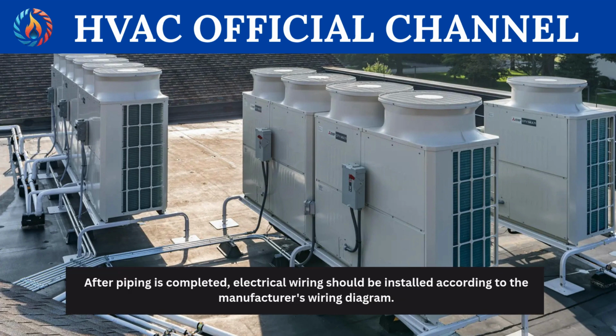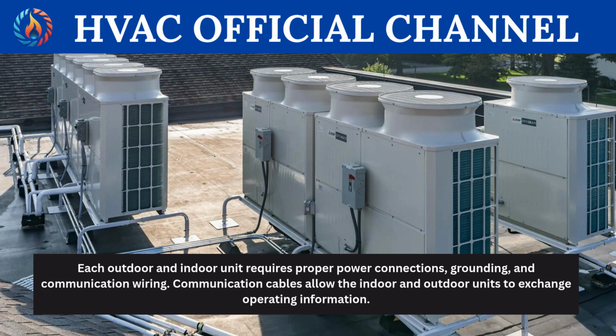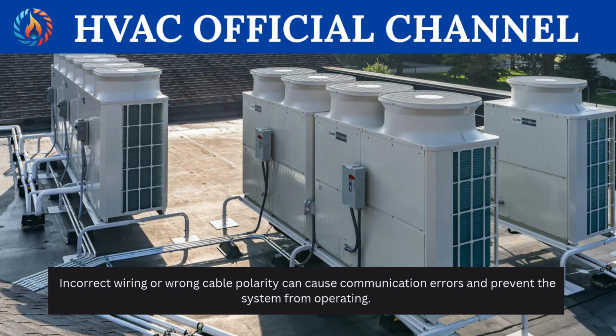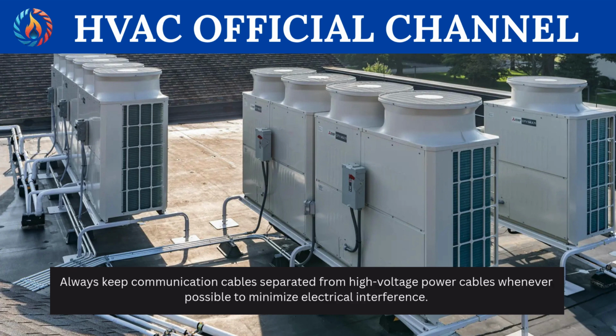After piping is completed, electrical wiring should be installed according to the manufacturer's wiring diagram. Each outdoor and indoor unit requires proper power connections, grounding, and communication wiring. Communication cables allow the indoor and outdoor units to exchange operating information. Incorrect wiring or wrong cable polarity can cause communication errors and prevent the system from operating. Always keep communication cables separated from high-voltage power cables whenever possible to minimize electrical interference.